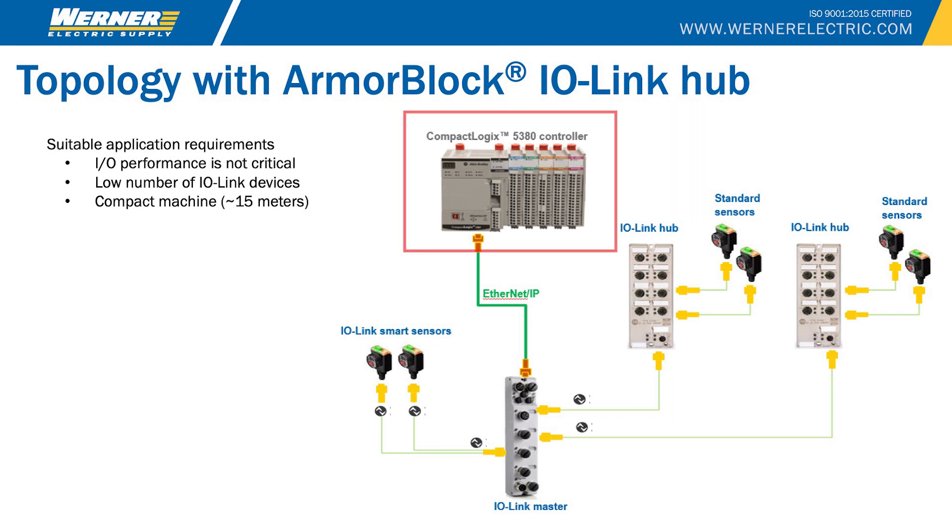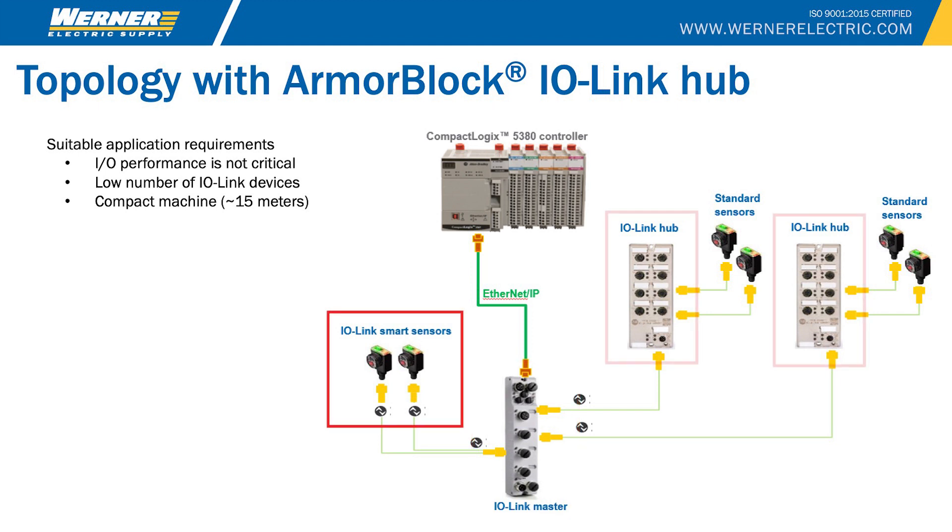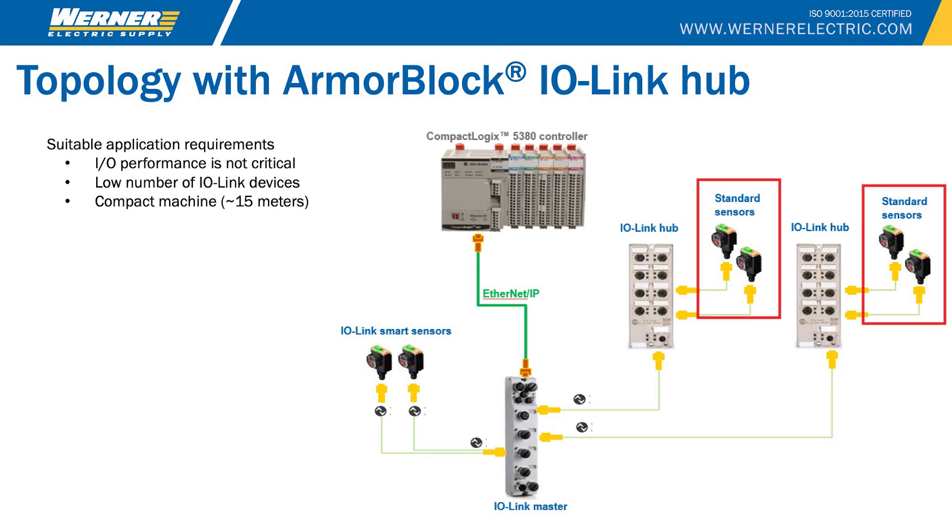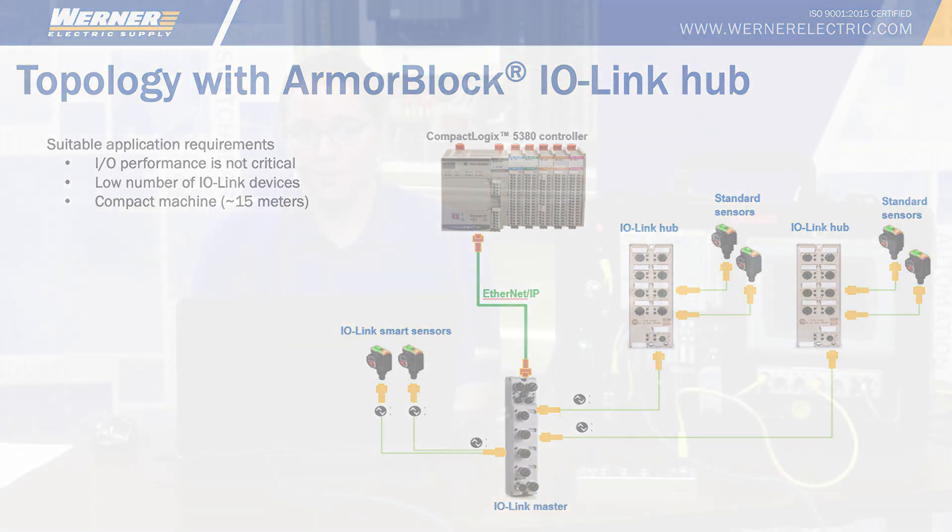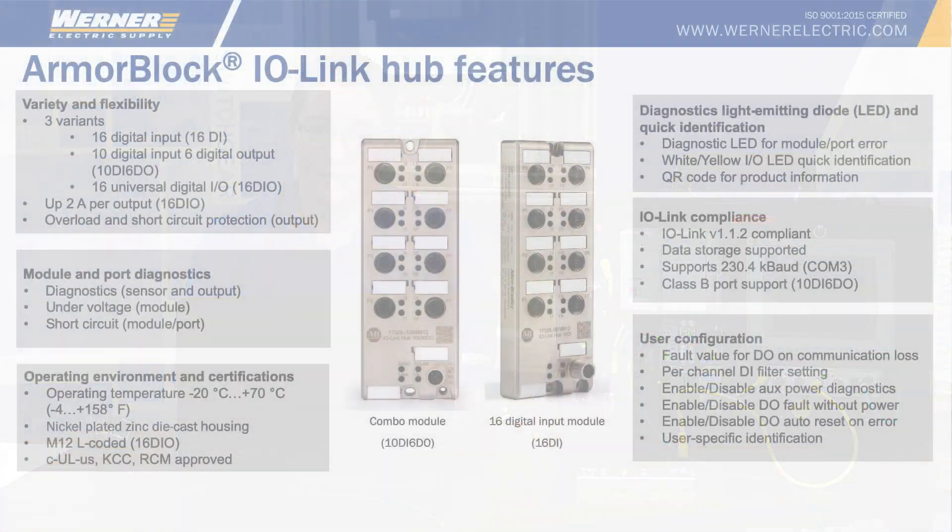Here we have a CompactLogix controller communicating via Ethernet to an IO-Link master. We have a couple of IO-Link enabled smart sensors connected. We also have two IO-Link hubs connected to the open ports of the IO-Link master. Standard discrete sensors are connected to these hubs. Utilizing this topology with IO-Link hubs allows you to add additional discrete IO into your control system without having to add additional discrete IO cards. This will allow you to save time in wiring and installation costs.